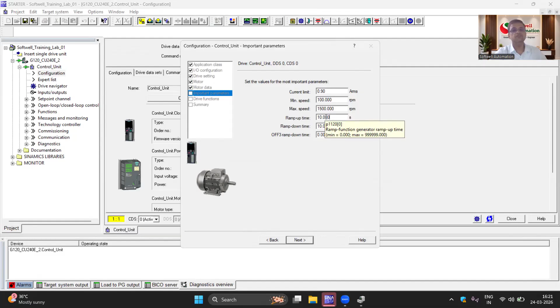Now, what is the application? Linear or parabolic. Parabolic means you want to use a centrifugal application. It means fan and pump. But right now, no load is connected to our VFD. For that case, we can select any one. So we are going to select parabolic right now, and then after confirm, auto tuning.